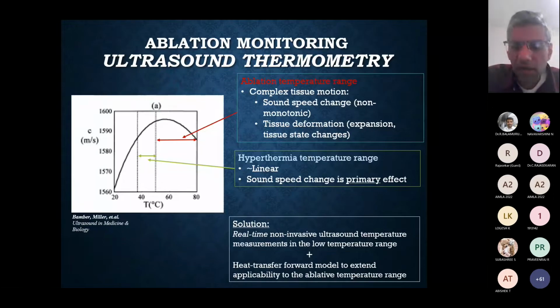Now I want to switch gears to one aspect of temperature estimation in ultrasound which needs special approaches. We've looked at this plot before, of sound speed versus temperature. It turns out that sound speed versus temperature is linear in the range between 40 and 60 degrees, but in the higher temperature range it's actually nonlinear, or more importantly, non-monotonic. So it's quite straightforward to measure temperature in the linear range, but not so easy in the range where it's non-monotonic.